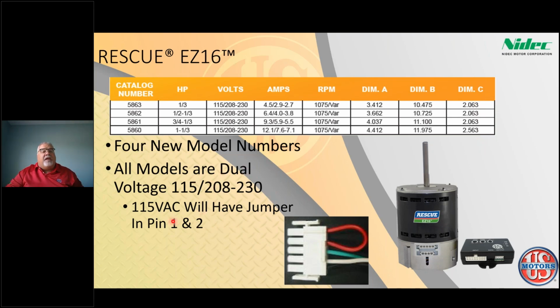One thing I'll mention is that it's dual voltage. There's no voltage change plug required on this product, because the actual plug tells it what the voltage is. If it has a little jumper between pin 1 and 2, that means it's 115. If there's no jumper, then it's 208, 230.